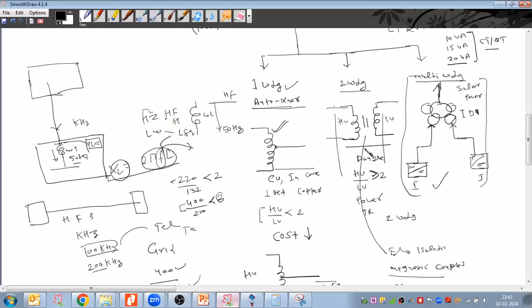Power from different PV tables is fed to one power transformer here, like a multi-winding transformer. Some power coming from this inverter could be 3.25 megawatt, and 3.25 megawatt coming from this, altogether 6.5 megawatt on the HV side, which we finally feed to the power transformer, stepped up and fed to the grid. I'm going to cover this in the solar SLD -- it will be more clear then.